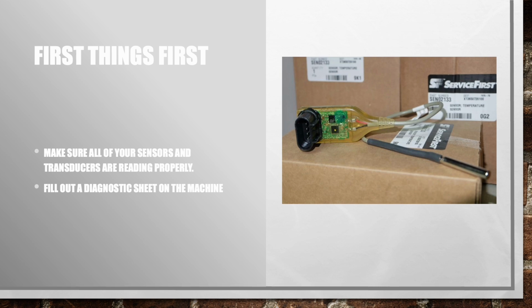So the first thing you've got to do is make sure everything's calibrated. Go through and get some ice water and calibrate all your sensors in ice water, and they should be within 2 degrees of 32 degrees, obviously. So plus or minus 2 degrees. If the unit has transducers, make sure all those are calibrated as well. Make sure they're within a PSI of the gauge you're using to calibrate with. And after that, go ahead and fill out a diagnostic sheet on the machine as well, so you can follow along and it helps with your diagnosing.